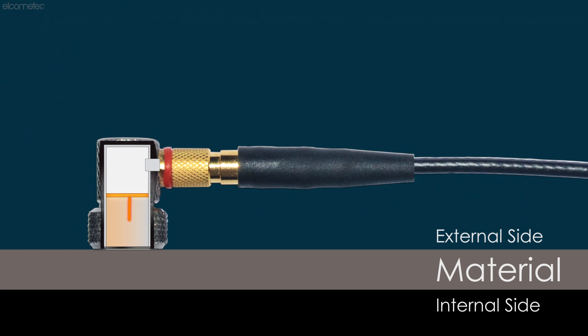The gauge then uses the speed of the pulse and the time taken between the pulse being emitted and the echo being detected to calculate the thickness of the material.